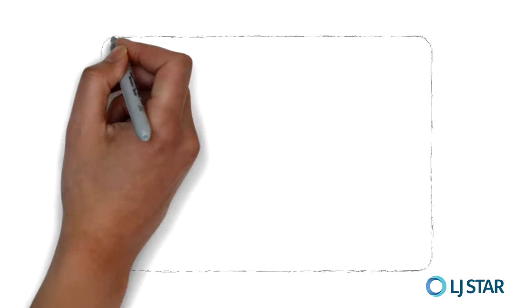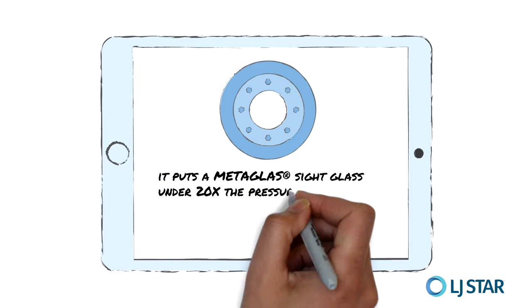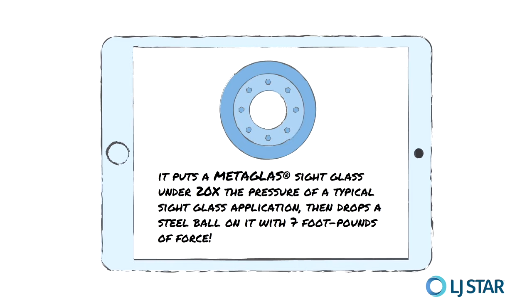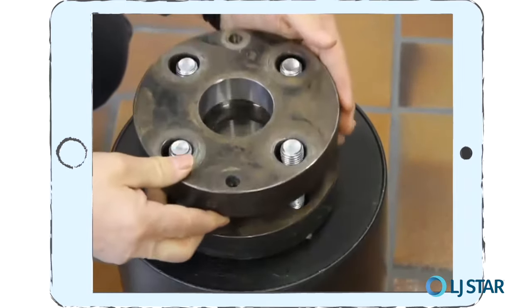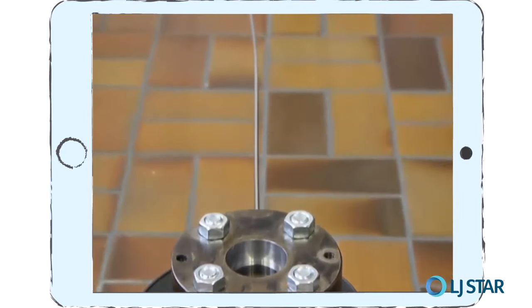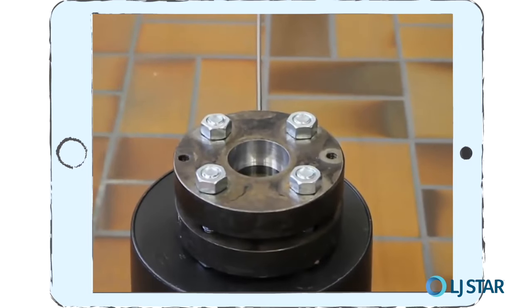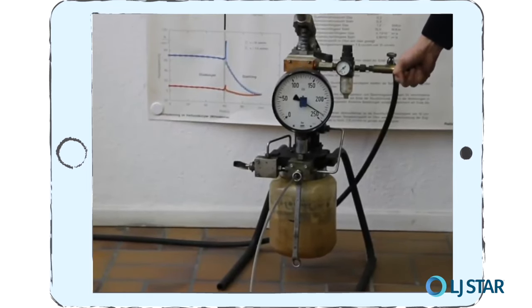Let's cover impact tolerance. Some of these processes demand the very best performance from your sight glass. Watch this test lab video — it puts a Metaglas sight glass under 20 times the pressure of a typical sight glass application, then drops a steel ball on it with seven foot-pounds of force. A seal gasket and Metaglas sight glass are positioned onto the base flange; a metal retaining ring and bolts hold it in place. A pneumatic pump connected via high-pressure tube increases pressure to 870 psi, then to 3,300 psi.